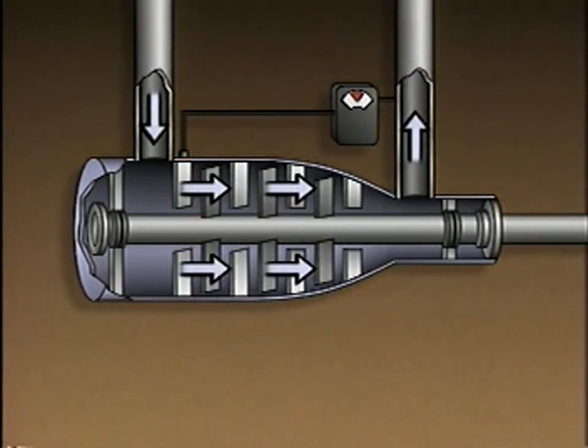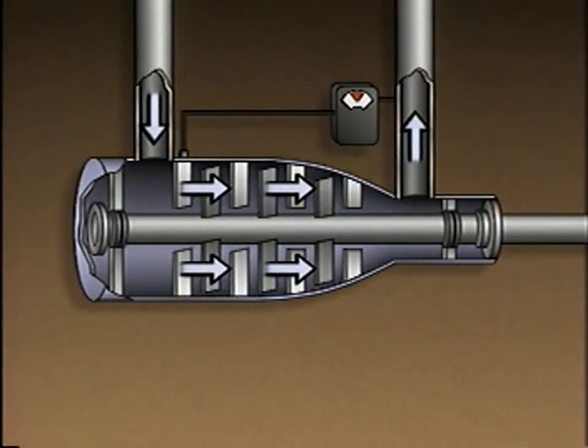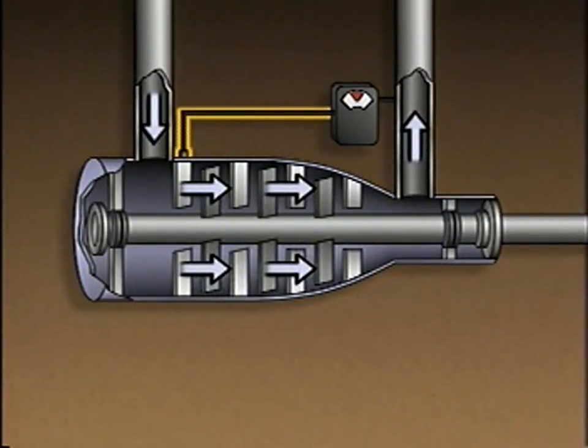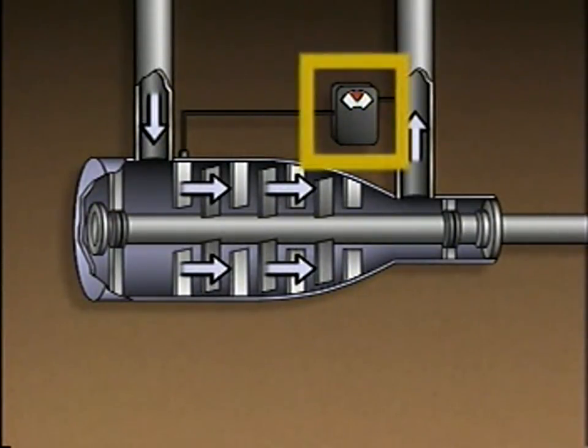The arrows indicate the flow path of the gas through the compressor. The pressure controller has a pressure sensor that senses the pressure of the gas in the compressor's discharge. If the discharge pressure deviates from its desired value or set point, the controller sends a signal that opens or closes the inlet guide vanes. As long as gas flow through a compressor matches the demand for gas, the discharge pressure also remains constant.